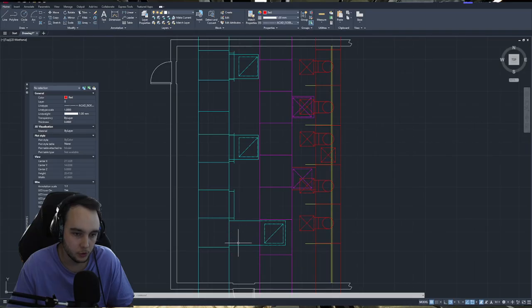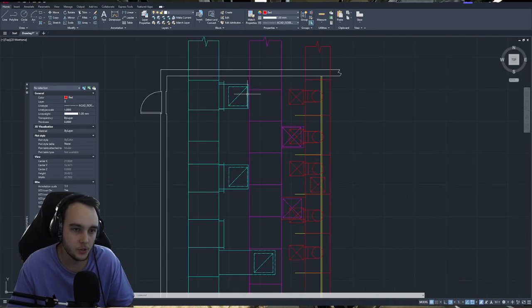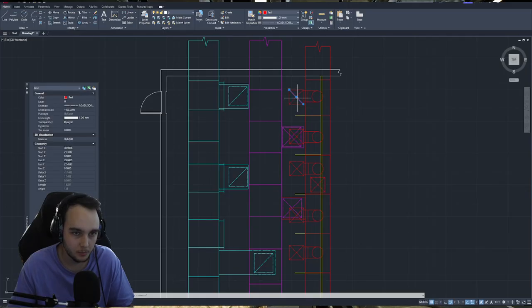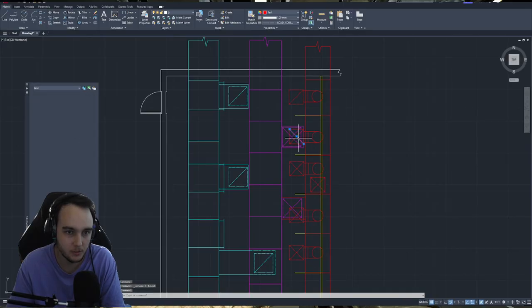And then we have one that just straight up runs from the return air, intersects into the supply air, and comes out the bottom. Looks really strange. Quick notation: typically when you do drawings showing diffusers or terminal devices, a solid single line diagonally like this typically means a return, and an X or a cross indicates supply. So air going in, which I screwed up because that should all be extraction.